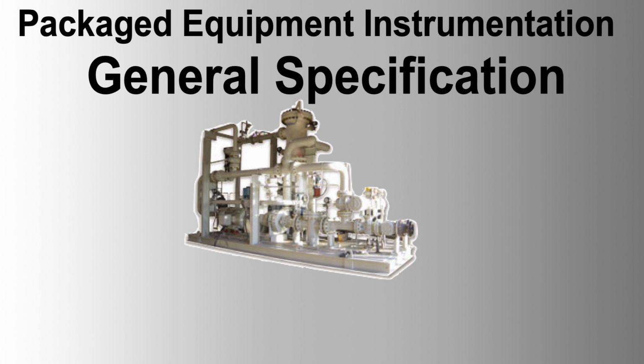Testing. Local control panel tests. Completed control panels and associated equipment must be inspected and tested to ensure compliance with specifications and drawings. This includes checking labels, tags, fuse ratings, circuit polarity, total electrical load, power factor, and earthing. Insulation test. All wiring must be tested for insulation with compatible test voltages. Circuits with insulation less than 10 megohms for 1 minute will be rejected. Sensitive equipment must be disconnected during testing.